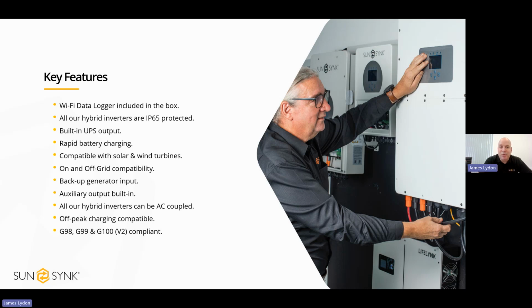Our hybrid inverters are compatible with solar and wind turbines, and it can be a combination of the two. If you've got a hybrid inverter with 2 MPPTs, you can have one for solar and one for wind. Wind is a lot more complicated than solar. But what gives us the USP on wind, built into the software of our inverter, is what's called a 12-point power curve. Wind turbines work similar to a bicycle gear mechanism.